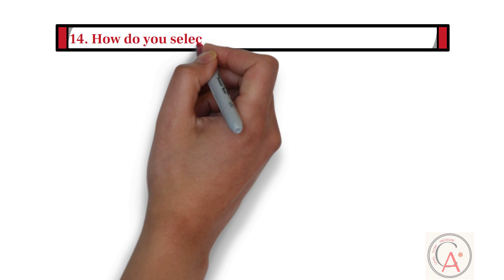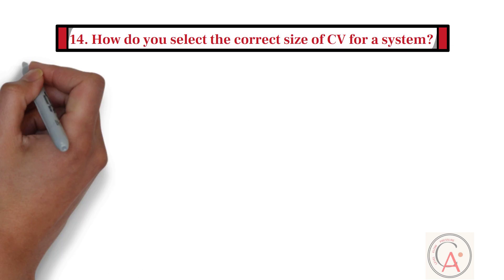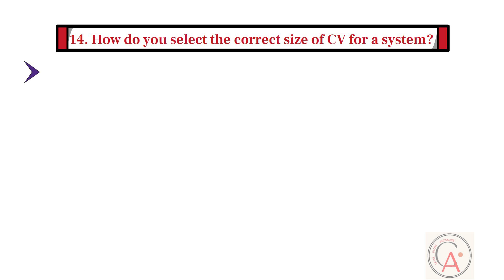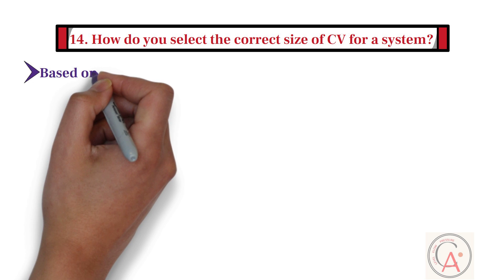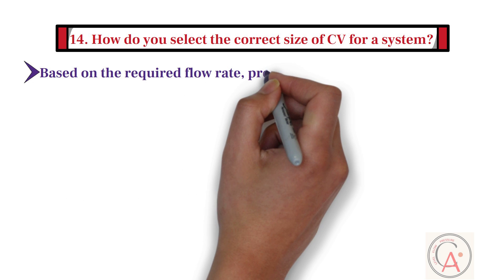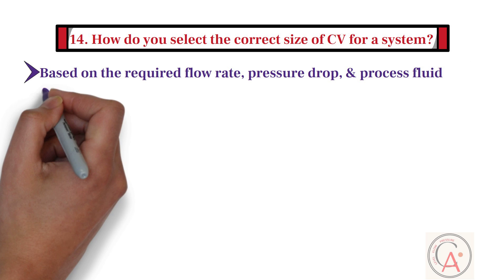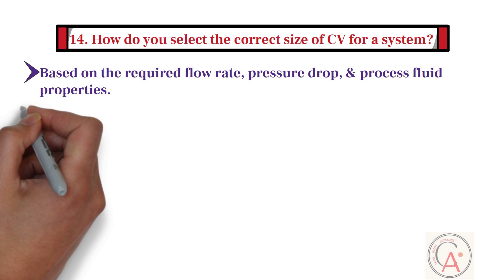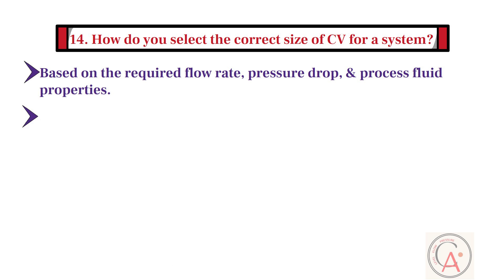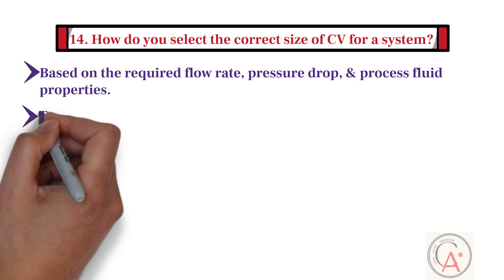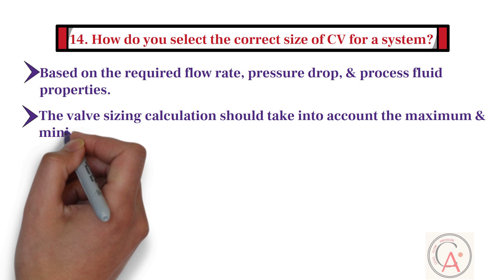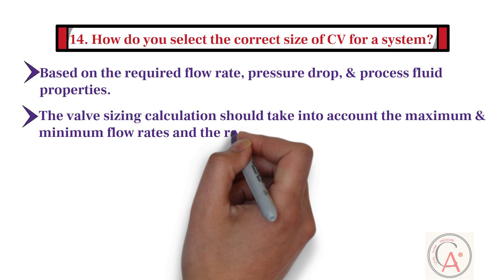Fourteenth question: how do you select the correct size of control valve for a system? The correct size of control valve is selected based on the required flow rate, pressure drop, and process fluid properties. The valve sizing calculation should also take into account the maximum and minimum flow rates and the rangeability required.